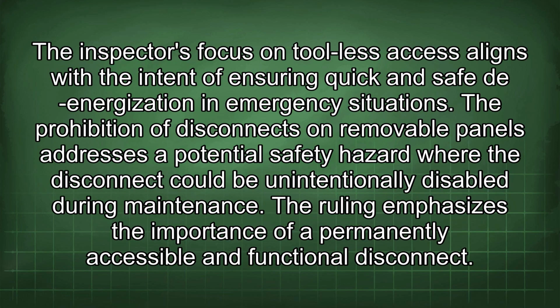The inspector's focus on tool-less access aligns with the intent of ensuring quick and safe de-energization in emergency situations. The prohibition of disconnects on removable panels addresses a potential safety hazard where the disconnect could be unintentionally disabled during maintenance. The ruling emphasizes the importance of a permanently accessible and functional disconnect.